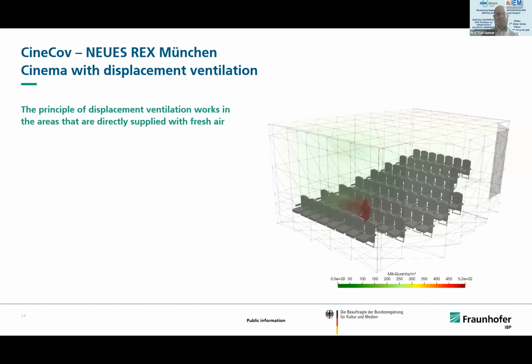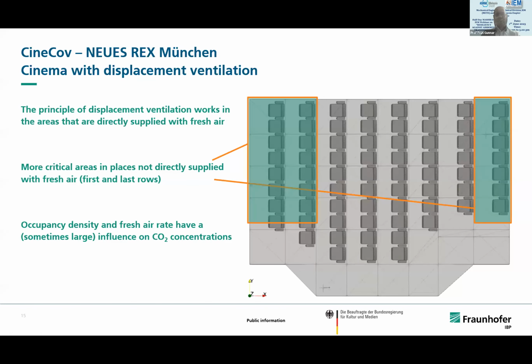The principle works very well in areas directly supplied with fresh air, for example at an index patient - here's one of our simulation cases where air is supplied under the seat and rises. It works more critically, not as well, in areas not directly supplied under the seat - typically the first and last rows. These are areas you have to watch out for carefully.